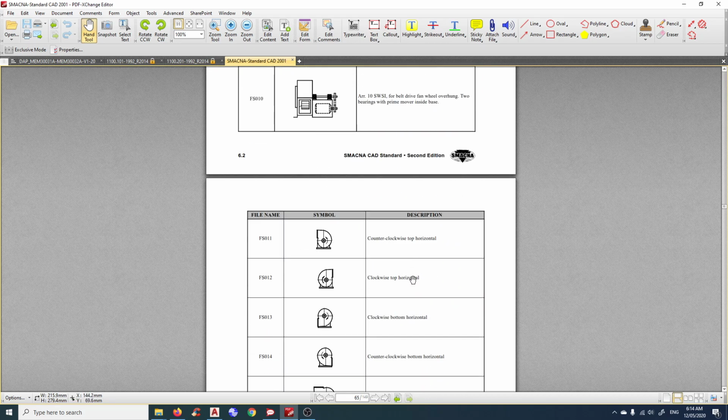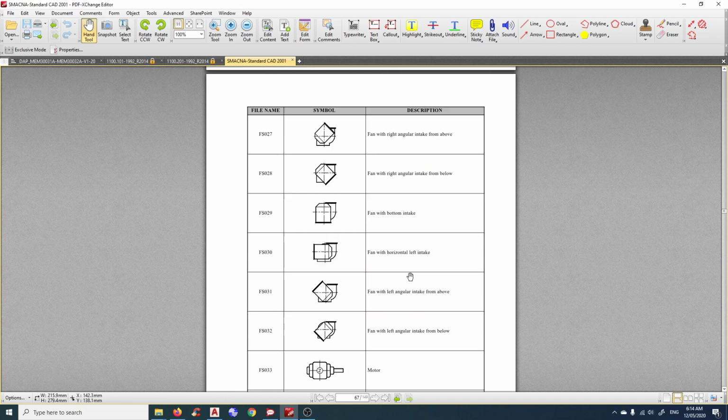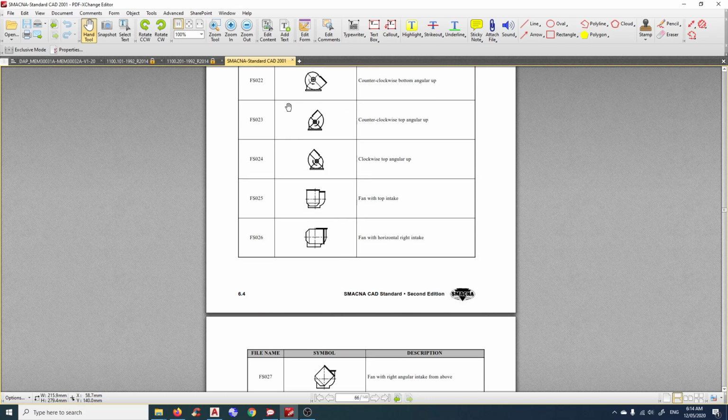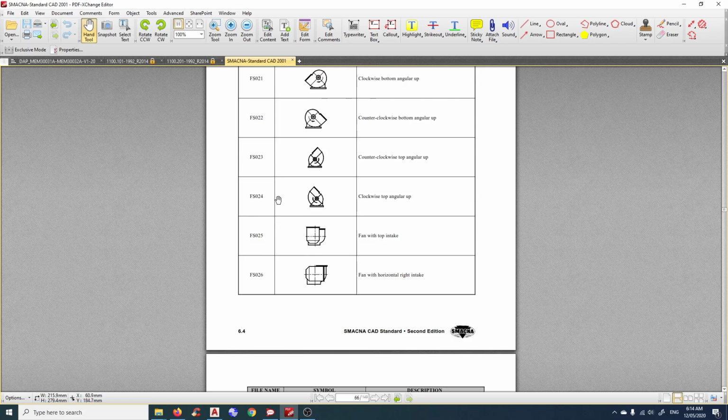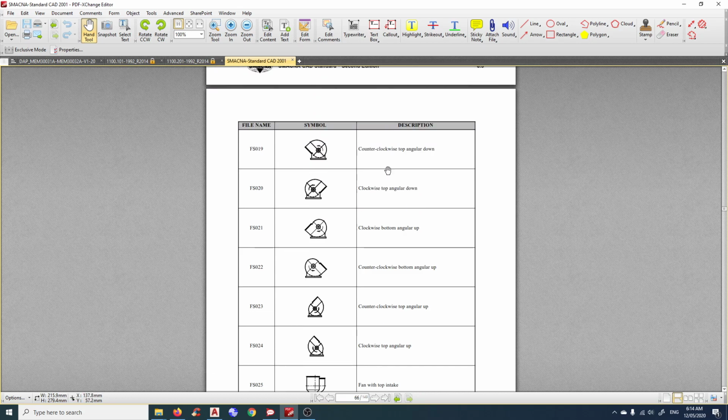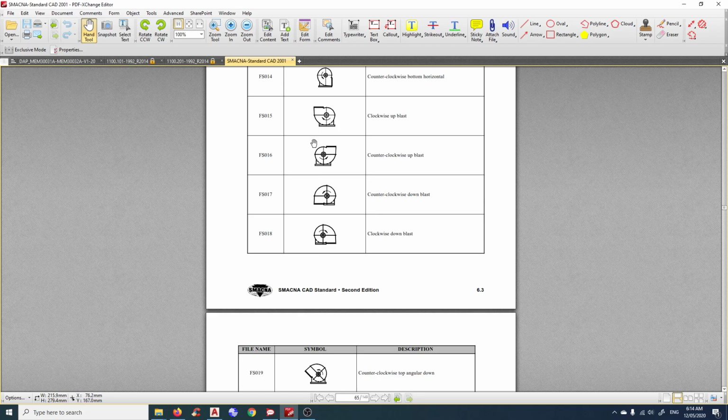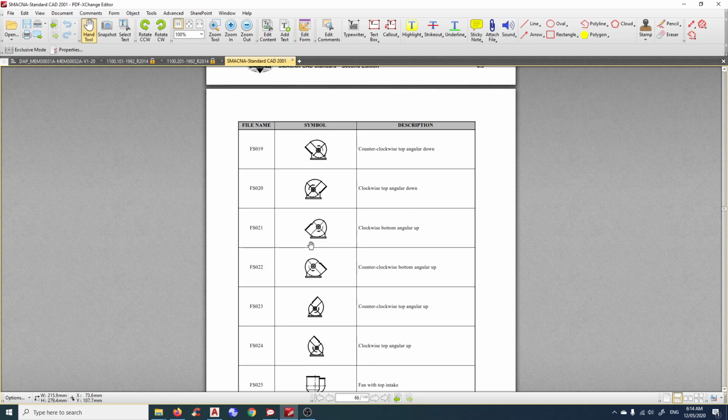Centrifugal fan, we'll skip that. Oh, by the way, this centrifugal fan symbol is used quite faithfully in the fan industry, so they're following the SMACNA standard. So if you see this symbol when you're ordering the fan, just be careful, check the rotation in your drawing, which way. If you are a contractor and you want to order the fan, always check this symbol. If we are consultants, we generally don't do this. We just want to say the airflow coming from the left has to go up.